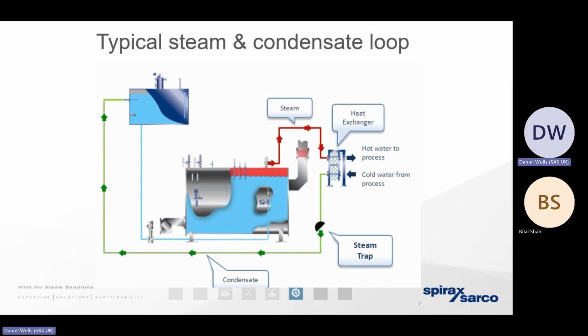So I'm going to use the example of a steam boiler operating at a pressure of 10 bar. So a 10 bar gauge, we're potentially going to have combustion gases at about 1600 degrees that are causing the water to boil off. And then we're going to have the combustion gases exiting the boiler and going up the stack into the chimney at approximately 200 degrees. Some boilers might have what we call an economizer on the stack, taking a little bit of heat energy from those combustion gases, so we can put that back into the water before it goes into the boiler. So we've got to put a lot of energy into the water, not just to bring it to the boil, but also so that that water is going to boil, evaporate, change state from a liquid to give us steam as a gas.